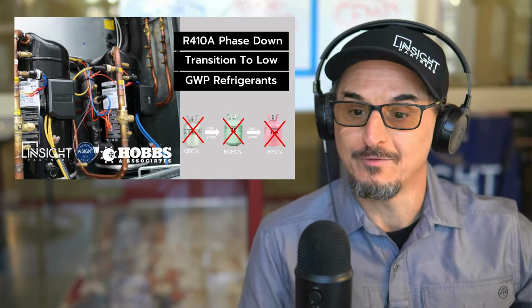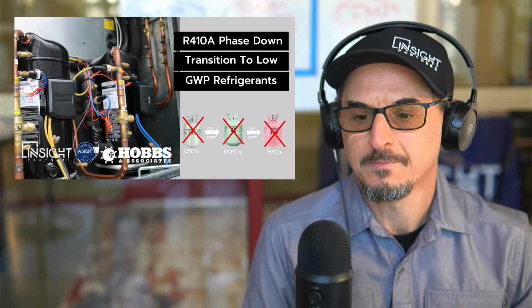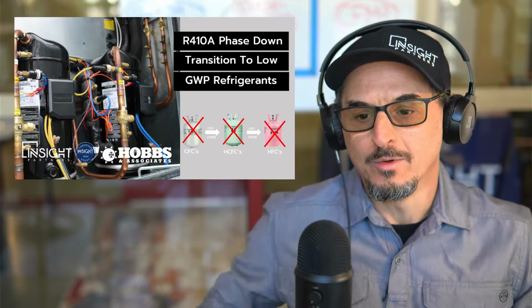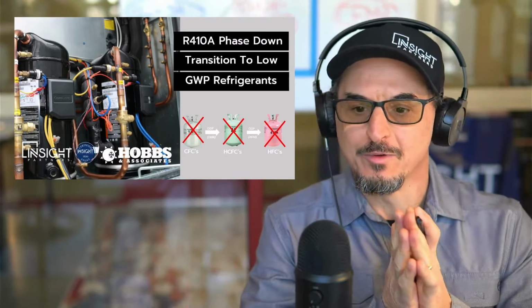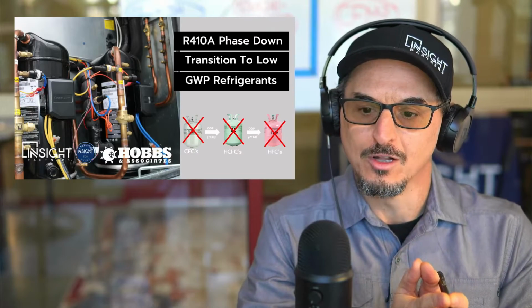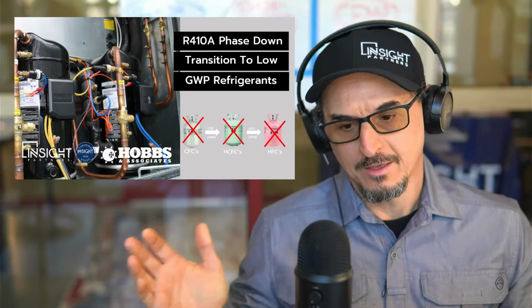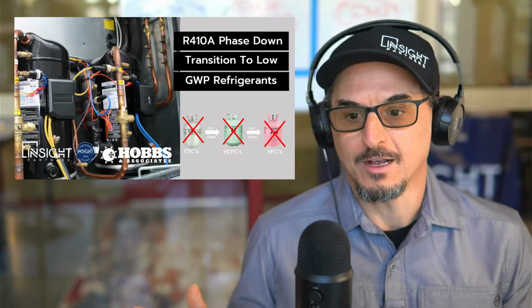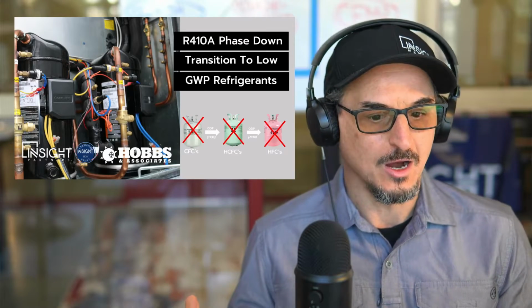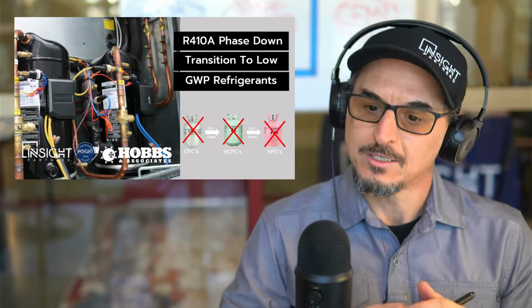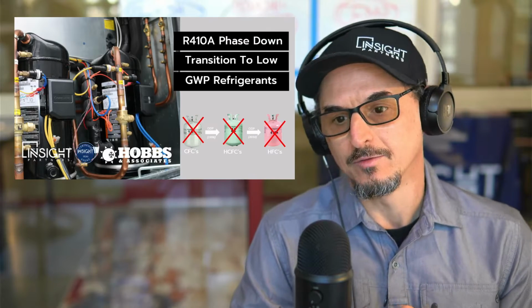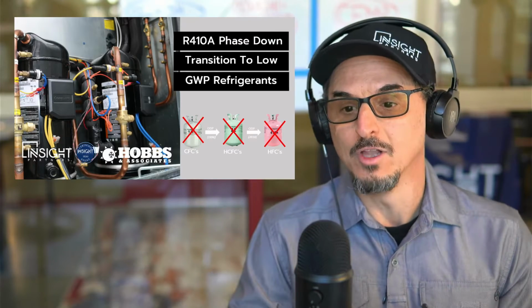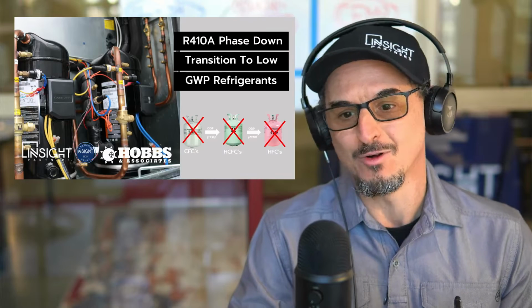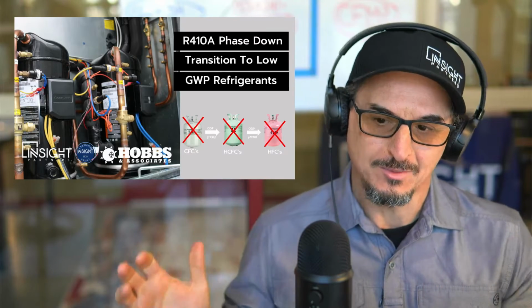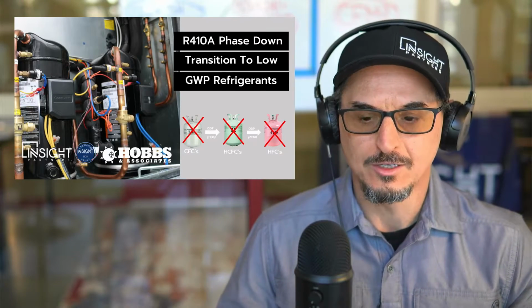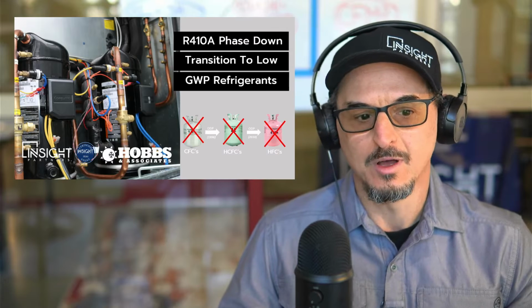If you're watching this and have any questions, please throw them in the chat. So when we talk about the transition to low GWP refrigerants, we're going to talk about what those two alternate refrigerants are. This wouldn't be that big of a deal, except the two alternate refrigerants are classified as A2L refrigerants, meaning they have low flammability on the ASHRAE 34 chart. That's really the biggest distinction as to what's happening, so I'll go over that.